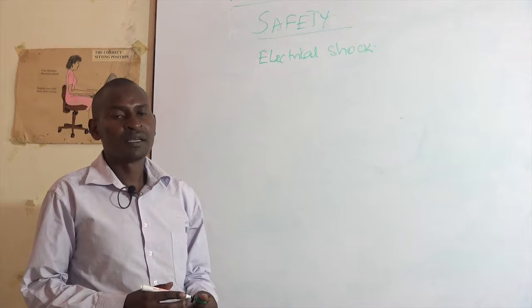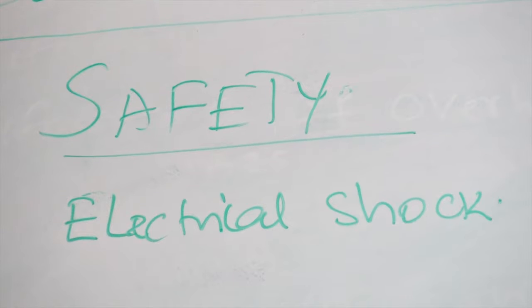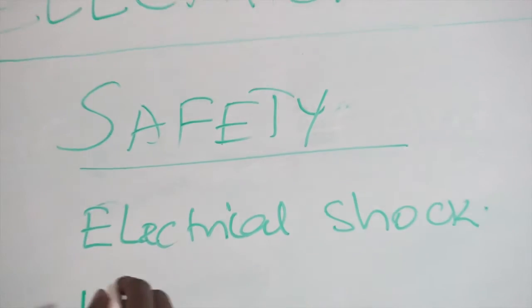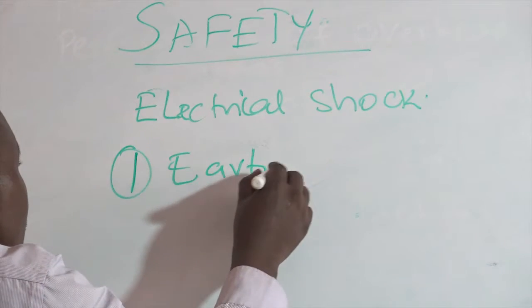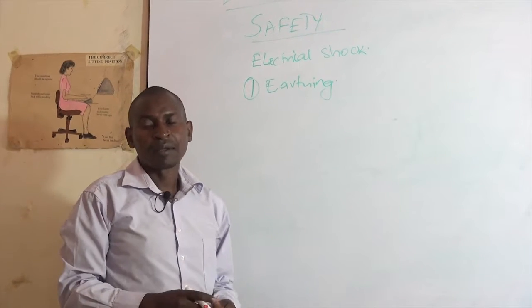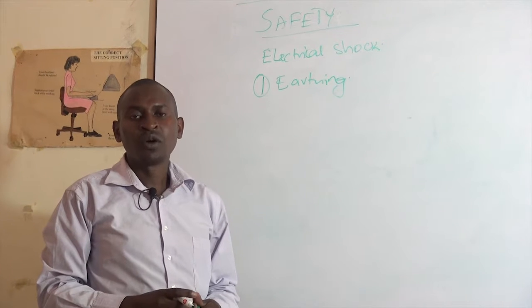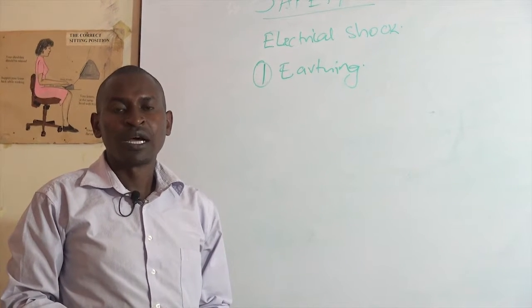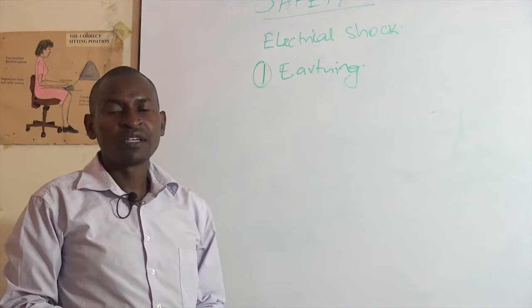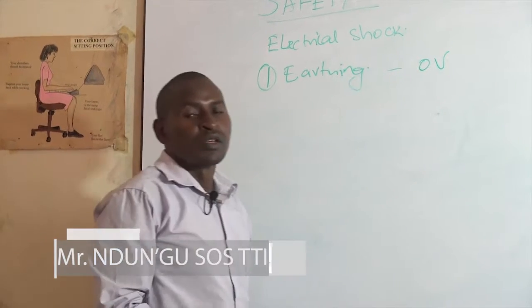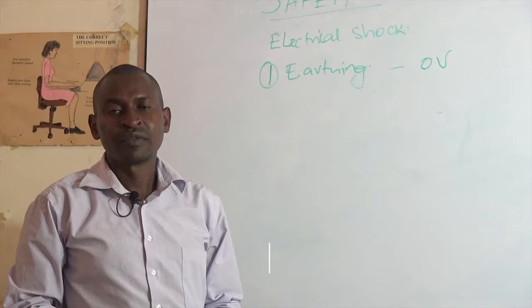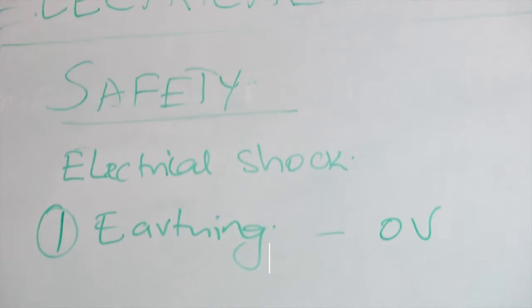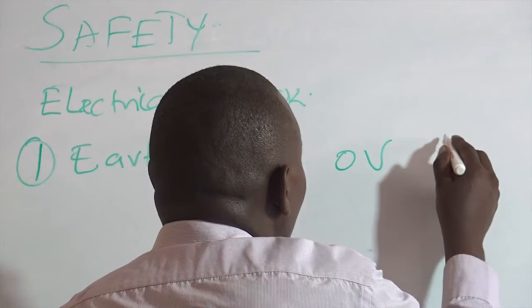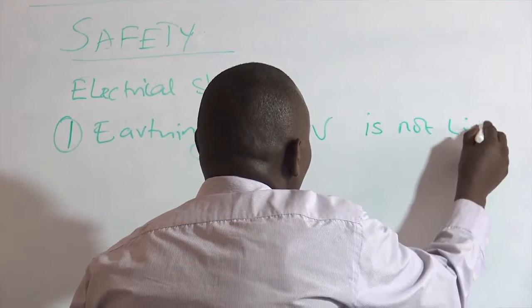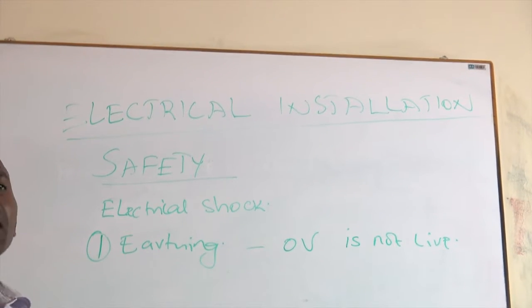So we see some of the steps that have been taken by the industry to reduce the risk of electric shock. Number one is earthing. Earthing is simply the connection of all exposed metalwork of the installation to the general mass of the earth. Naturally, the general mass of the earth is at zero potential. So when anything is connected to the general mass of the earth, it is going to be at zero potential, meaning that it is not live, or it cannot be live.